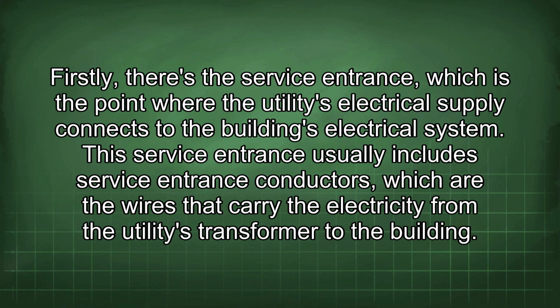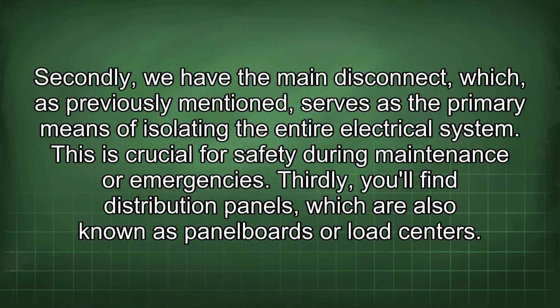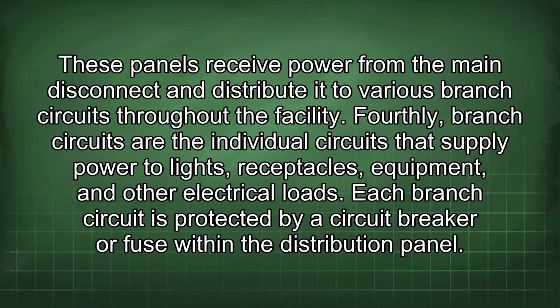This service entrance usually includes service entrance conductors, which are the wires that carry the electricity from the utility's transformer to the building. Secondly, we have the main disconnect, which, as previously mentioned, serves as the primary means of isolating the entire electrical system. This is crucial for safety during maintenance or emergencies. Thirdly, you'll find distribution panels, which are also known as panel boards or load centers. These panels receive power from the main disconnect and distribute it to various branch circuits throughout the facility.